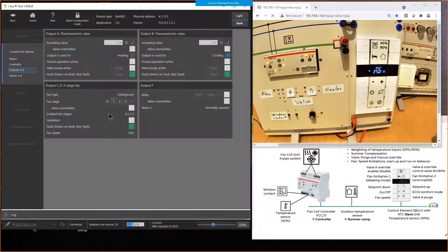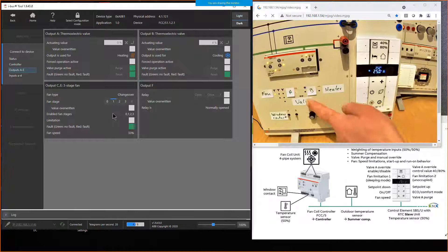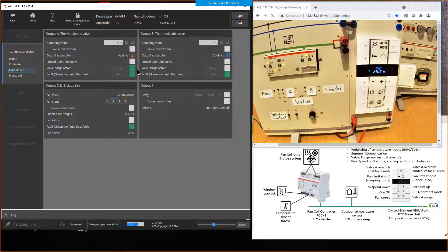For the valve purge demonstration — we can use it automatically every four weeks via internal timer, or trigger it via a group object like a time switch. When I click this button, the valve purge for valve output A starts. You see the output activates, the valve starts, and the valve purge is now active — shown by the green icon. The valve opens one time so it does not get stuck, for example during summertime. After the time set in the ETS, the valve closes automatically. That is the principle of the valve purge.